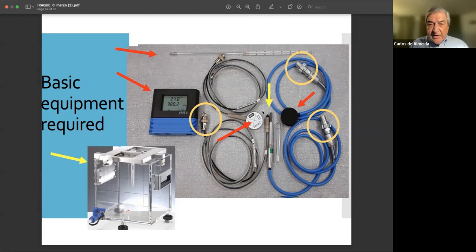You see this cable has a cap, and this one doesn't have a cap. And let me tell you something, all those connectors must have a cap to avoid humidity problems. If you don't have a metallic cap, you just put aluminum foil and a rubber band around it and keep it safe, okay? This is most likely the highest point of problems in our ionization chambers, not only in the cables, but also in the electrometers if they're not kept in a place where humidity, dust, and so on are controlled. Next one.